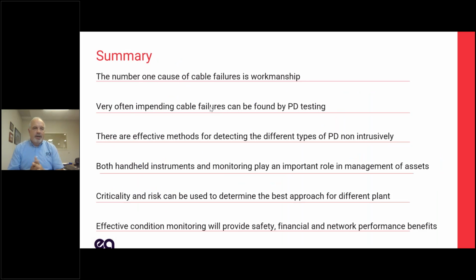So, last slide: the number one cause of failure, and some of the things we learned here today. The number one cause is workmanship. We know that very often impending cable failures can be found by PD testing. There's a variety of tests you can do non-intrusively without taking a cable out of service. Instruments are great for the asset management aspect of it, and you need to look at criticality and risk. If I've got a cable that's feeding a little podunk situation down the road, that's a little different than if it's feeding Wall Street, or a data center floor. So you need to weigh risk into it.